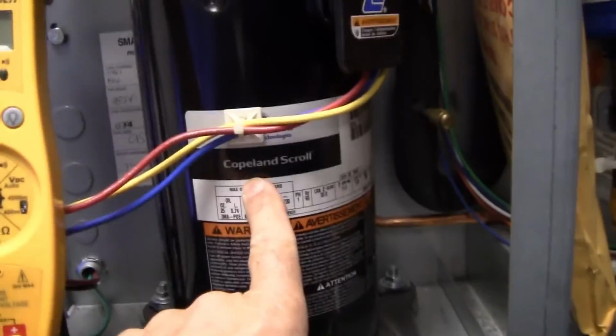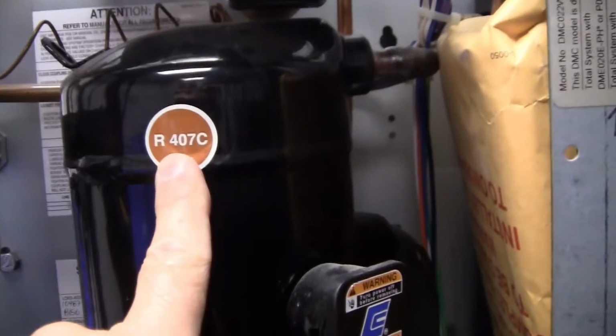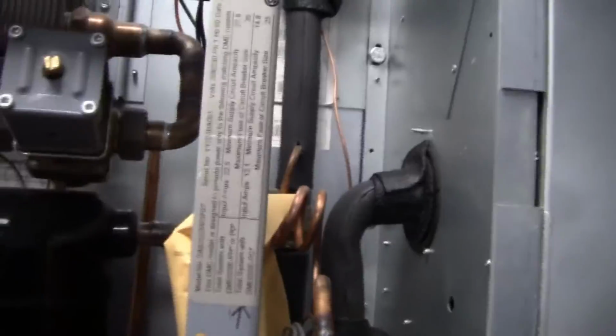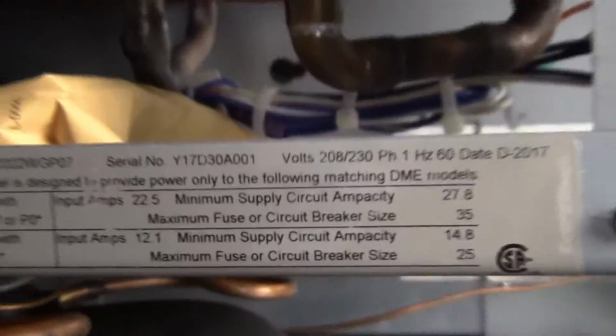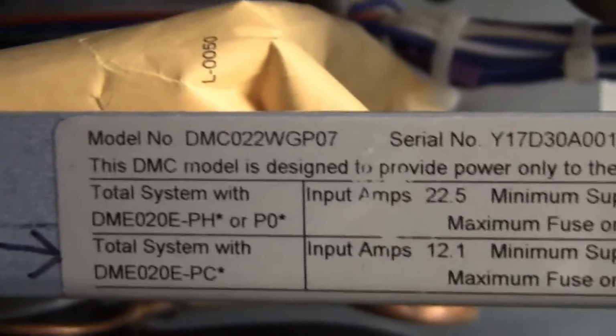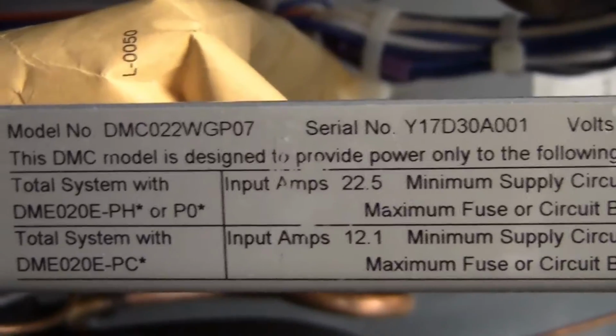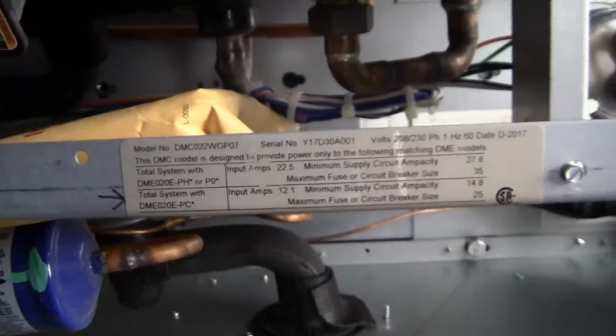Right? I can hear the ice dropping out of the coil because this thing had been running so cold. You can't really see the ice here, but I guarantee you there's some ice on the back side of that. I can hear it dropping inside the compartment. Okay, so by the way, as long as I'm here, as you can see, it's a Copeland scroll compressor. Refrigerant is R407C. Here is the data plate for the condensing section. Let me just turn that upside down so you can see it. And there's your model number and your serial number of this particular unit. This unit is 2017.